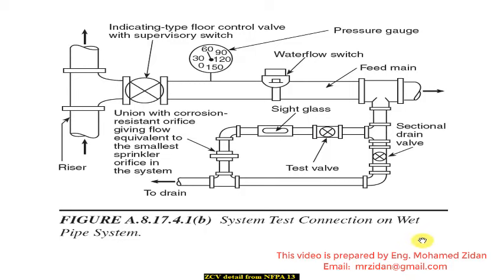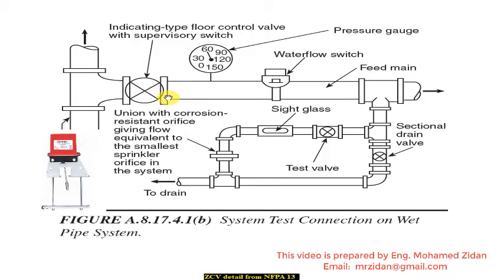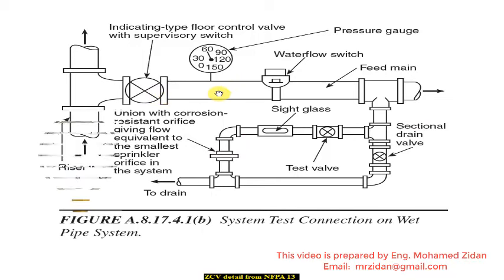I will explain the components of the zone control valve as per NFPA 13. This is the water firefighting riser, which is coming from the firefighting pump and going to the different levels. From this riser we will have a T-connection to a specific zone. After this T, we will have a set of valves and sensors called the zone control valve set. The first item is the indicating floor control valve, which can be an OS&Y gate valve or butterfly valve, and we install a tamper switch on this valve. After that we will have a pressure gauge.